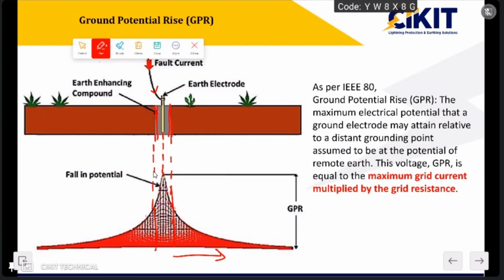And if you closely observe this, the potential near the earth electrode will be very much higher, and if I move away from this earth electrode, the potential will be very much lower. So the sudden increase in potential during this discharge of fault current will be considered ground potential rise. If we are mentioning a sudden increase in ground potential, there has to be some comparison. So here the comparison will be between the potential of this particular earth electrode and the potential of any remote earth electrode. In the general case, we have the potential of earthing as 0 volt.